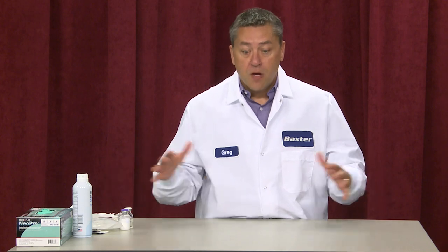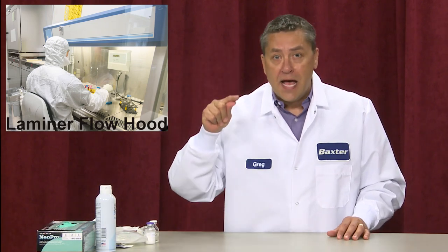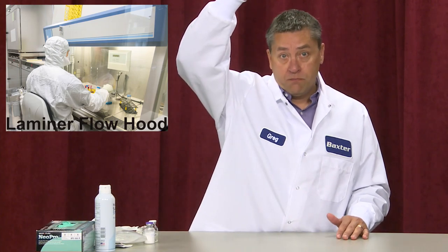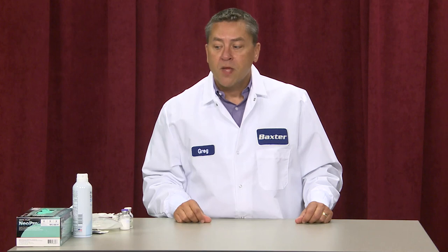What we're going to do first is introduce what we're going to pretend this is — we're pretending this workspace is a laminar flow hood. You might have seen some hoods in your chemistry laboratories or at different companies. This particular hood has air flowing in one direction using a high-efficiency particulate air filter, also known as a HEPA filter. This air is coming from one direction, from the top down. That's very important because this is similar to what occurs in the manufacturing area around any product that is exposed to possible interactions.